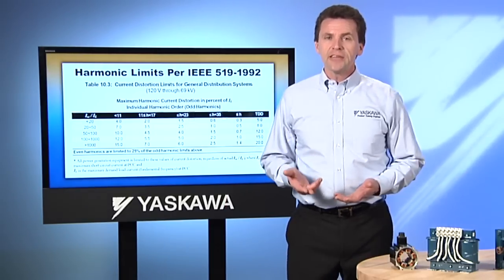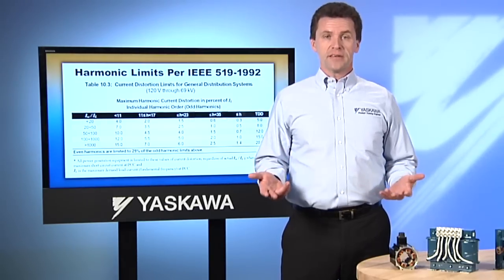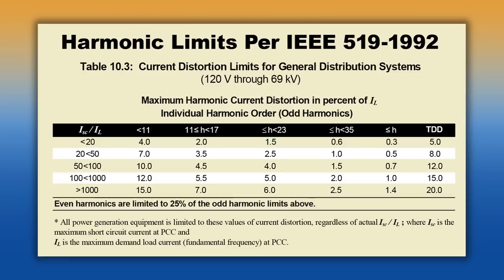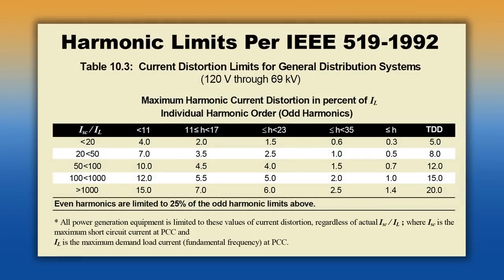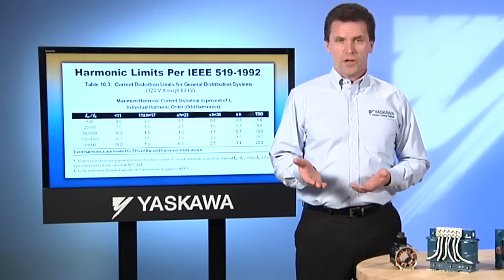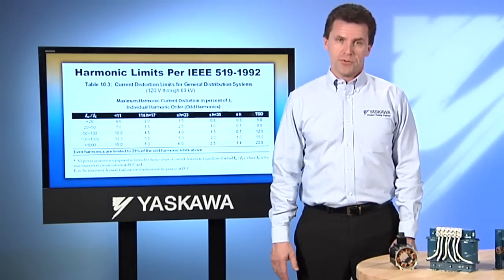The value of THD on a cycle-by-cycle basis is not meaningful when the main intent is to reduce power loss and reduce heating in the power delivery equipment in an optimal way. The 519 standard calls for measurement at the point of common coupling with the utility, but engineers specify its use at the input terminal of the variable frequency drives. This standard is often too rigorous, but it's so commonly used that it is important to address its abuse.